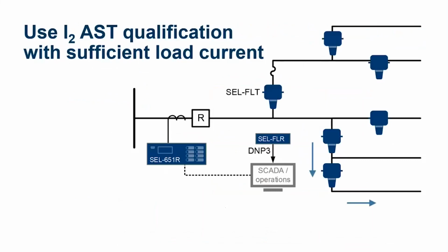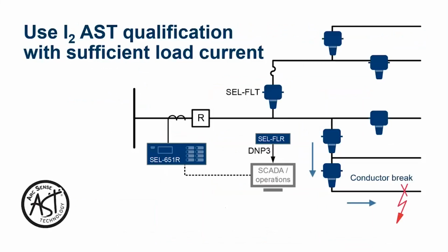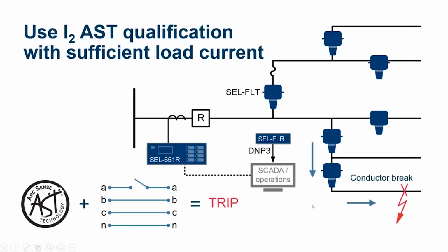So let's look at an example here. In this case, we have a conductor break and an associated high impedance fault, with the conductor laying on the ground on a heavily loaded lateral circuit. We are able to detect the arcing associated with the high impedance fault in our 651R. Also in the 651R, we have a qualifier that looks at the ratio of negative to positive sequence current. We have a significant amount of negative sequence current in this case because this is a large percentage of our loading. And so we make a decision to trip, because that's most likely a down conductor. And we can provide that information to SCADA so that they can see that we tripped and that there's potentially a down conductor in that location.